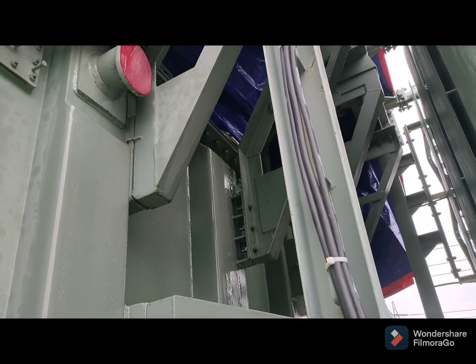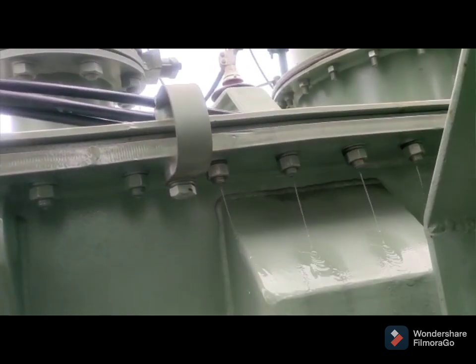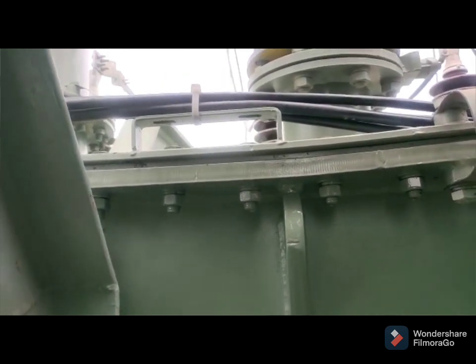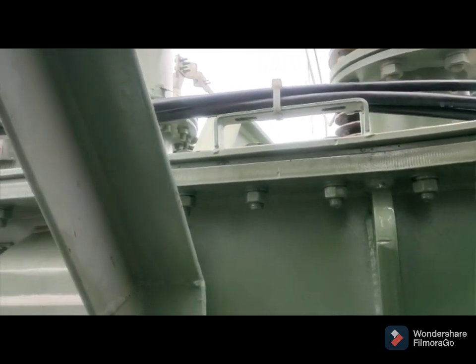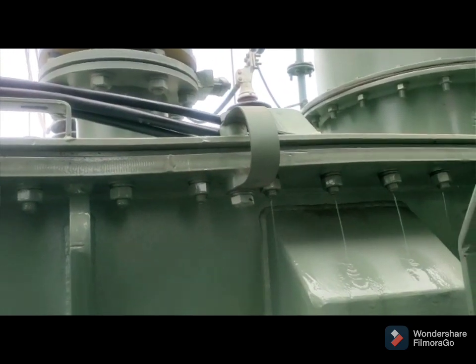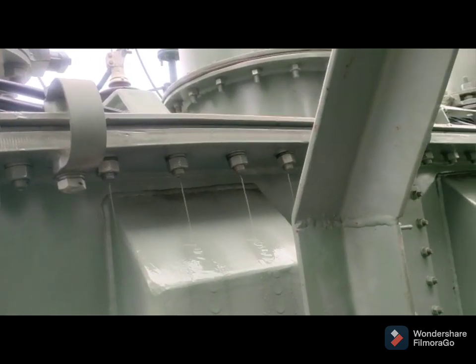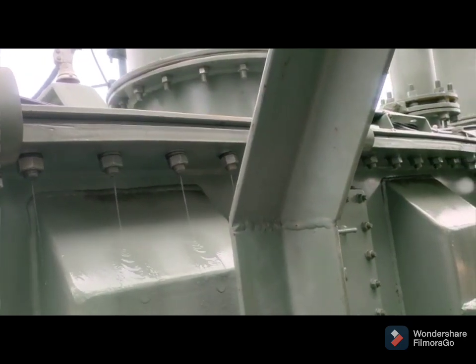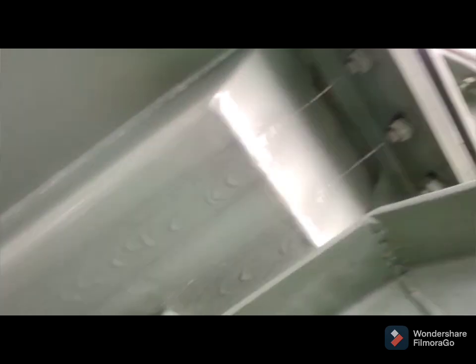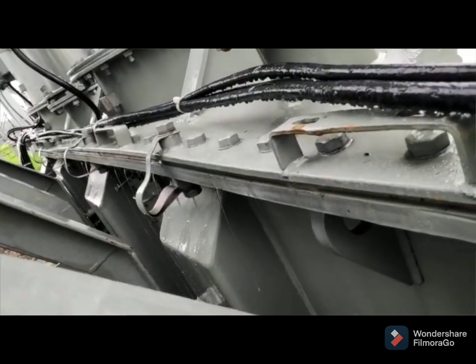This is the oil dropping video, and this is the bending position near the yellow bushing — the upper plate and the lower plate have been bent. You can just observe how the bending occurred and how the oil is just dropping from the transformer. 16,000 liters of oil are inside the transformer for insulation and cooling purposes.